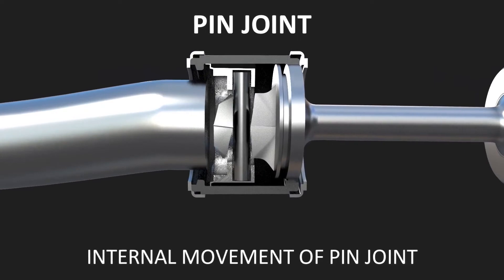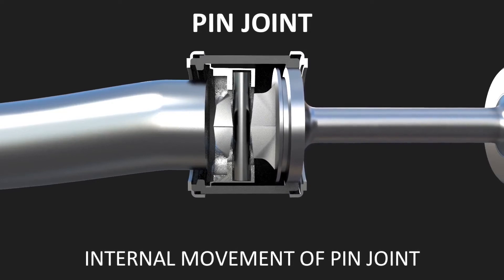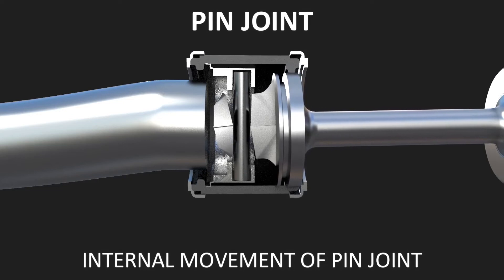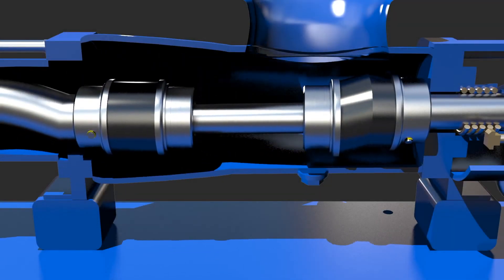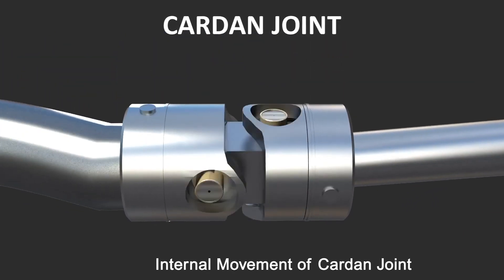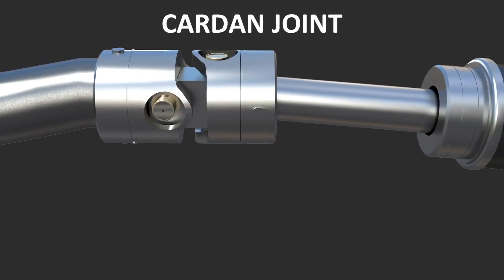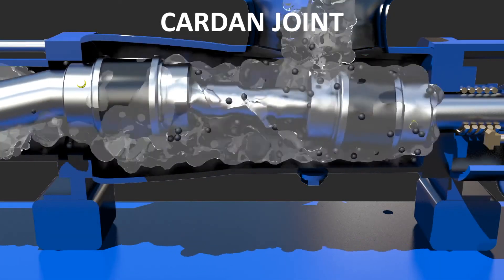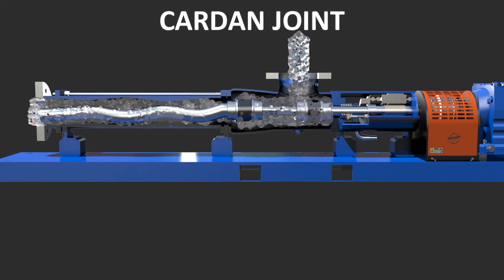In a typical progressive cavity pump, the pin joint is the weakest link, as it has to absorb eccentric radial and axial forces, resulting in premature wear or failure — especially if the product is abrasive. The MXQ PC pump has two Cardan joints, which more efficiently distributes the eccentric radial and axial forces into several components, allowing for greater angularity. All components are lubricated with a heavy synthetic temperature-stable lubricant and enclosed in an elastomeric boot made from the same material as the stator.